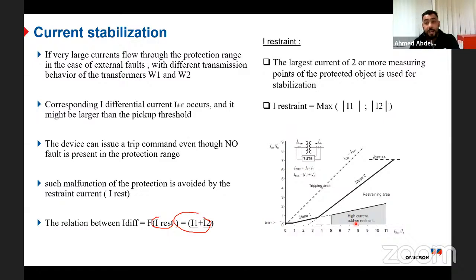And the other case is an external fault where one CT is saturated, because the restraint current starts increasing at the very beginning, then later on the differential current starts increasing. Then the relay will try to block the differential protection for a certain time. And if this time elapses, it means we need to trip to avoid any failure in the protected zone. This is how the idea of current stabilization happens, and also the dual slope characteristic.